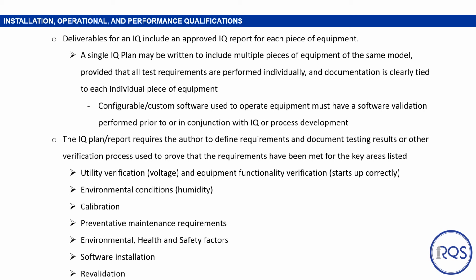The IQ plan report requires the author to define requirements and document testing results or other verification processes used to prove that requirements have been met for key areas listed below. That includes utility verification such as voltage, and equipment functionality verification such as the equipment starting up correctly, any applicable environmental conditions such as humidity, calibration, preventative maintenance requirements, environmental health and safety factors, software installation, and then of course the times in which revalidation may be needed, and that should also be documented.